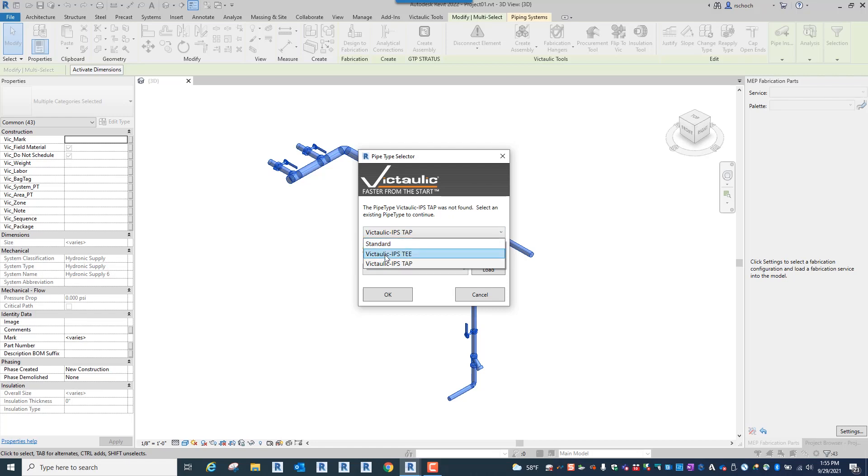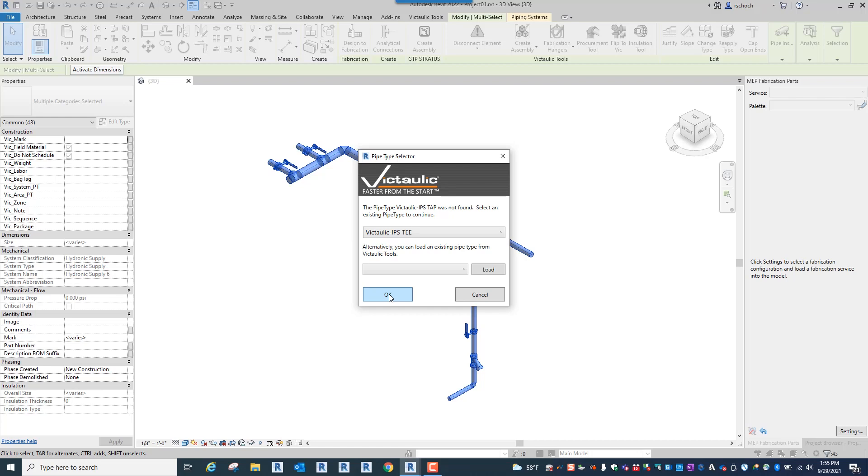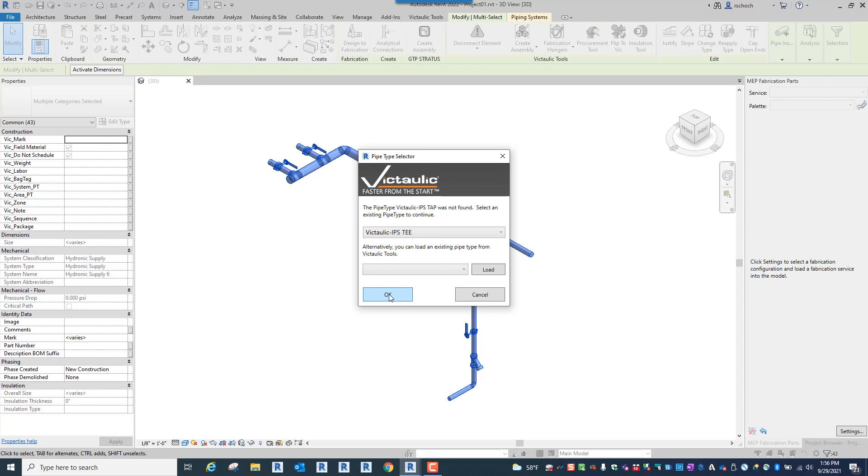Now I can select in this case I'll select the IPS TEE and then generally I do recommend most people take the model and convert it to tee. If there's areas that you want tap then you can select the tap pipe type later. The way Flip2Vic works is it wants to keep the piping in the same location it's in. So we made some rules that when it does the conversion any pipes that are there it's going to keep those center lines. It's going to work really hard to keep them. So if it can't keep them because of fitting to fitting issues what it'll do then is just disconnect it at that location and give you a log that you can go down through.